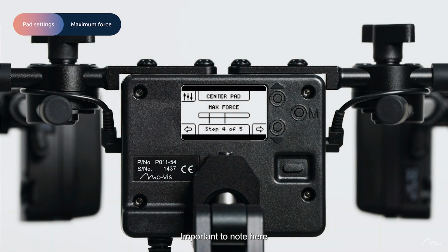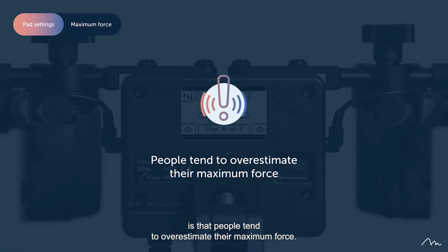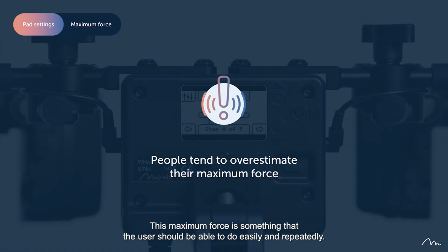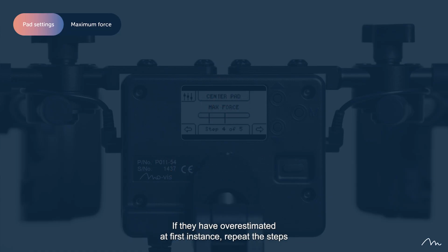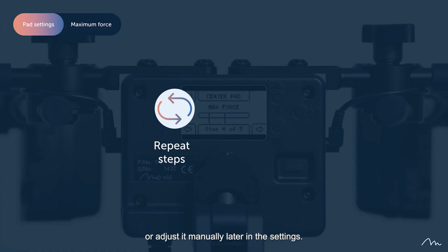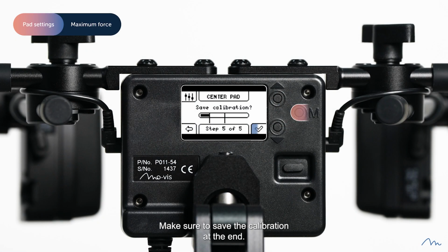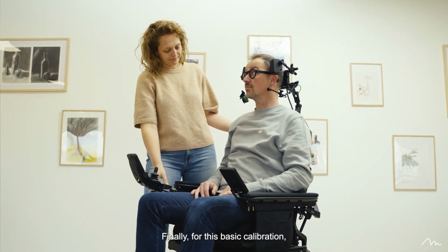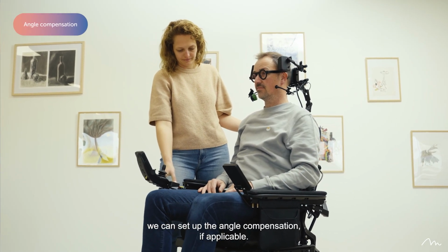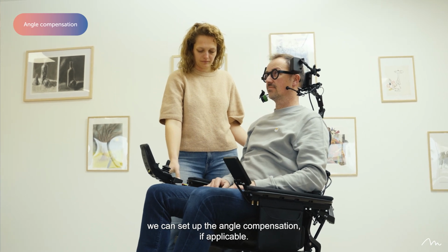Important to note here is that people tend to overestimate their maximum force. This maximum force is something that the user should be able to do easily and repeatably. If they have overestimated at first instance, repeat the step or adjust it manually later in the settings. Make sure to save the calibration at the end. Finally, for this basic calibration, we can set up the angle compensation, if applicable.